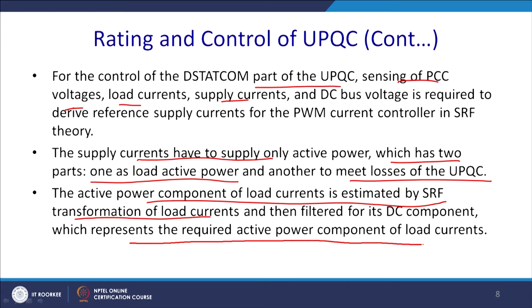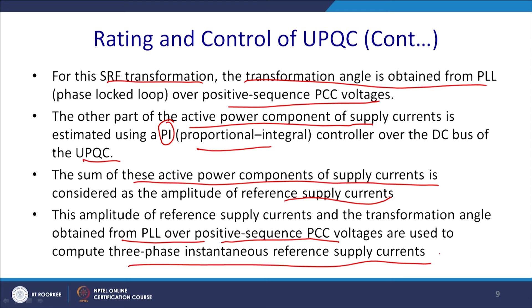For the SRF transformation, the transformation angle is obtained from the PLL, phase lock loop, over the positive sequence of the PCC voltages. The other part of the active power component of the supply current is estimated by using a PI controller or PID controller over the DC bus voltage of the UPQC. After describing, I will explain the block diagram of it. The sum of these active power components of supply current is considered as the amplitude of the reference supply current. This amplitude and the transformation angle obtained from the PLL over the positive sequence PCC supply voltage are used to compute the 3-phase instantaneous reference supply current. In that way you can compute the 3-phase reference supply current with the SRF.